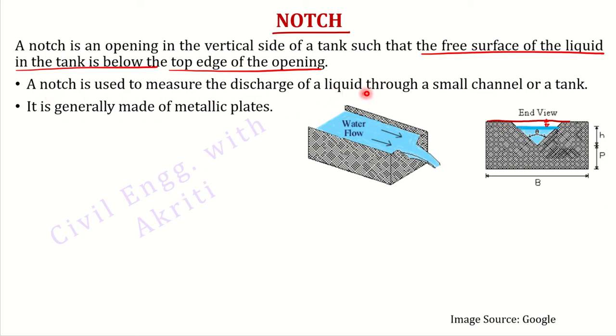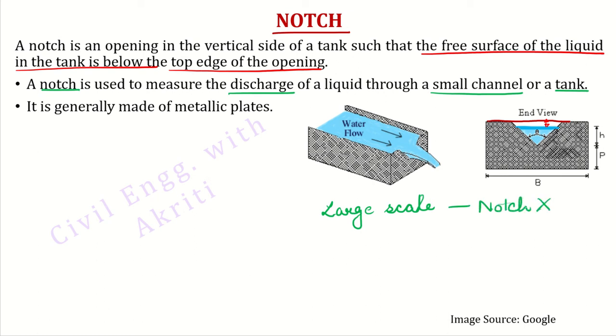A notch is used to measure the discharge of a liquid through a small channel or tank. Notch large scale ke liye preferred nahi hota. Agar aapke bahut badi river ya bahut badi open channel hai, toh aap notch ko prefer nahi karenge. Notch is only for small scale measurement of discharge. Isliye, kyunki small scale measurement hai, hum notch ko metallic plate se banaate hain — metal ka bana hota hai, kyunki iska purpose small scale discharge measure karna hai, ya small scale channels, pipes, ya tanks ke liye hai.